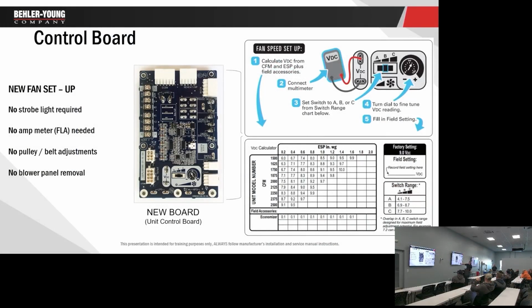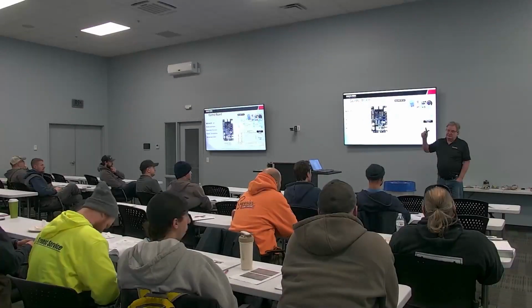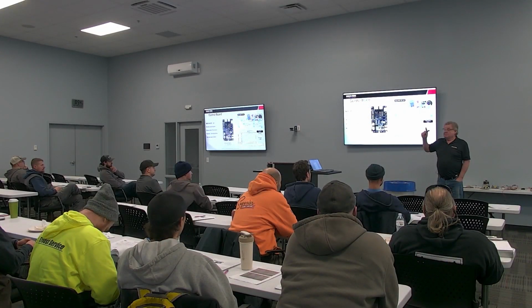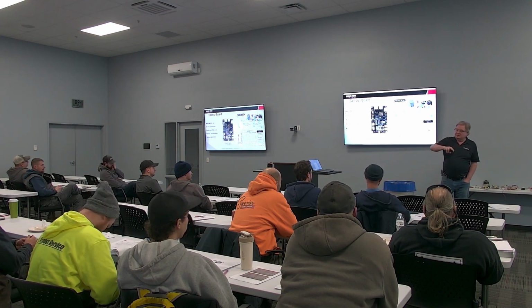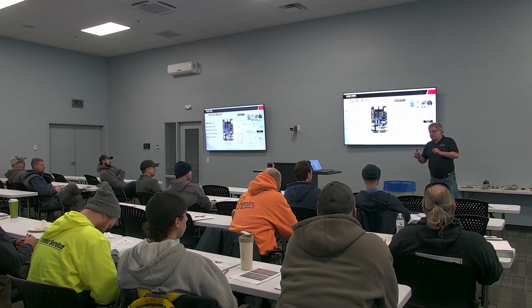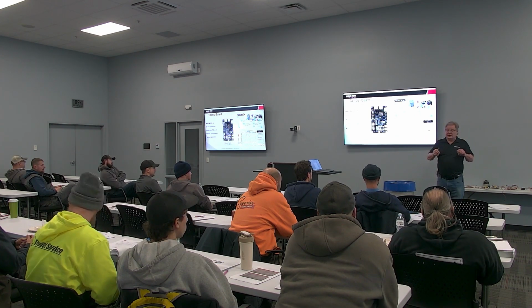This tag is also on the control box of that unit, and it's going to tell us how to set the static on this unit. Before we set the static, what is the first thing you do on a rooftop unit when you turn the disconnect on? Very first thing. Check the primary voltage going to the transformer. Does everybody do that? That's a multi-voltage transformer. It's either 230 or 208, and it's tapped from the factory at 230. If you have 208, guess what happens? I don't have 24 volts. I have 22 or 21, 23. I have low voltage, and I start eating contactor coils.